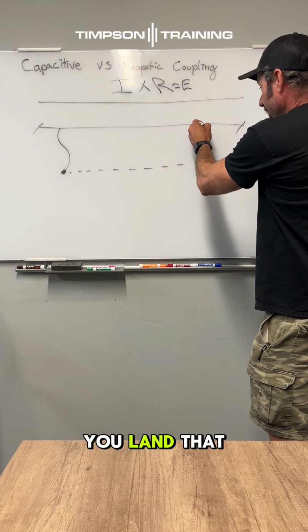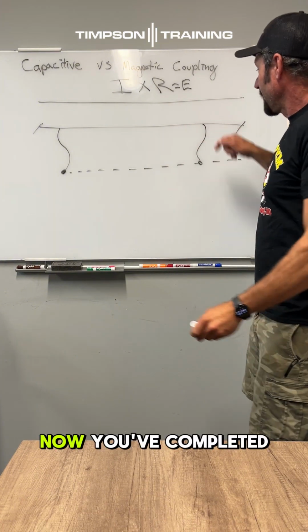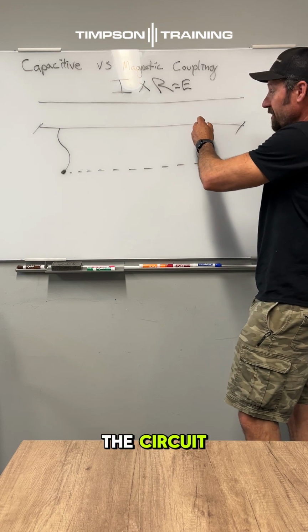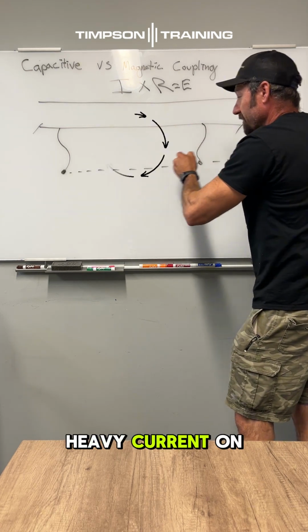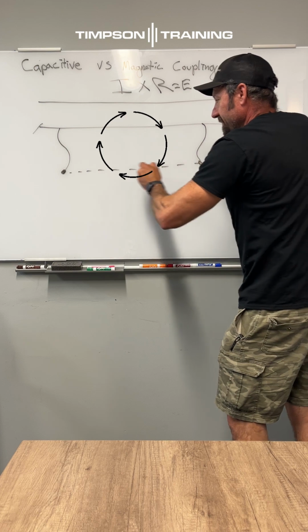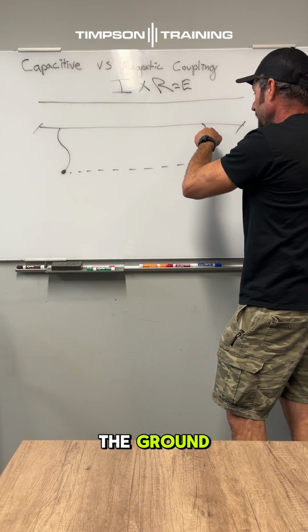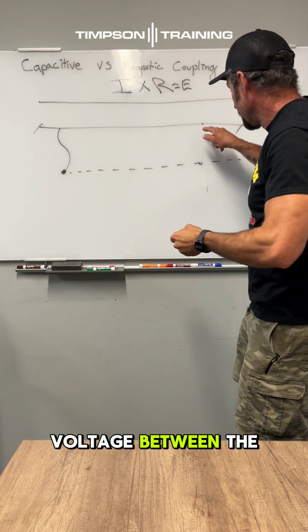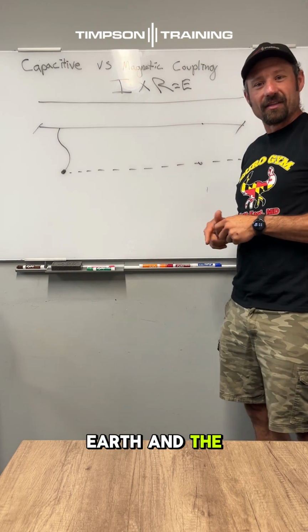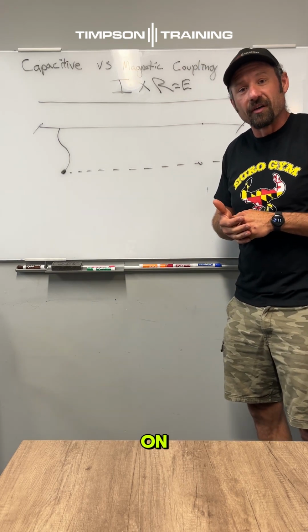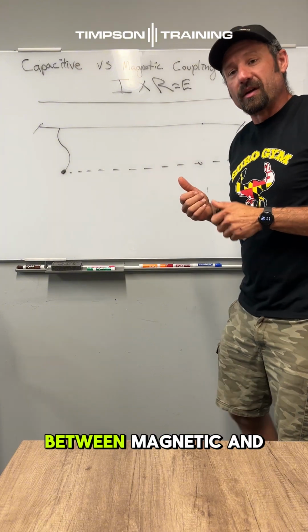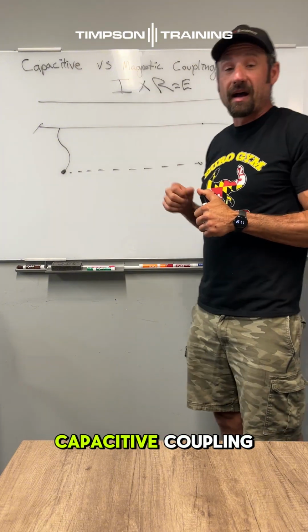Here, when you land that ground, now you've completed the circuit and you have heavy current on the line that circulates. If you remove the ground, you have a voltage between the earth and the conductor that you're going to be working on. And that's the difference between magnetic and capacitive coupling.